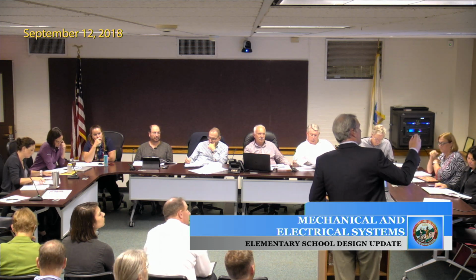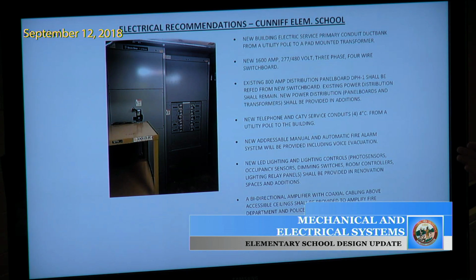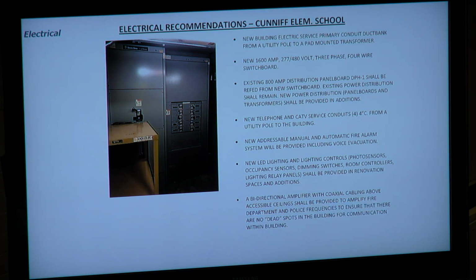On the electrical recommendations, again, I broke this down by schools. There'll be a new building electric service. For example, on the Cunniff, the existing switchgear is 800 amps. It's not enough capacity to support a modern school with the technology and the air conditioning that goes into a modern school. So our office has proposed a new 1600 amp, 277/480 volt switchboard. We would then backfeed that back to the 800 amps. So the 800 amp stays in place. We just backfeed it with a 1600 amp. So you get a brand new electric service brought in.